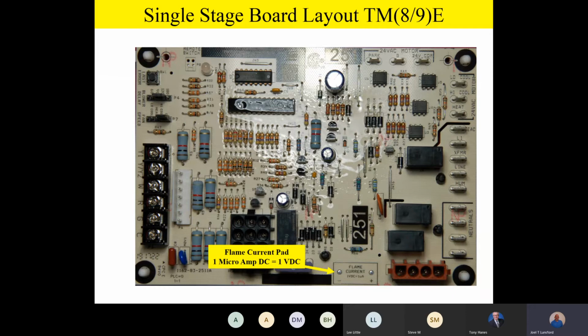Now remember, team, 1 volt DC is equal to 1 microamp flame current. And so again, 1 volt DC is equal to 1 microamp flame current on that flame current pad. Now please write this down or make a little note. When you're troubleshooting our furnaces, typical flame current should run between about 3.5 to 4. So about 3.5 to 4 would be normal. If it falls below 1.5, you're going to get an amber flash code. And if it falls down to 0.1, that's 1/10 of a microamp, it'll go ahead and lock the furnace out.